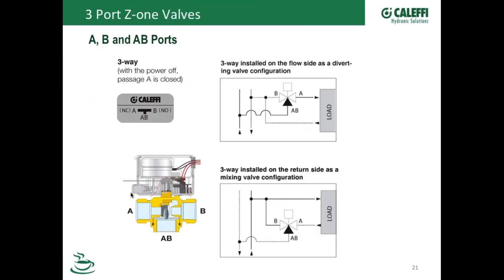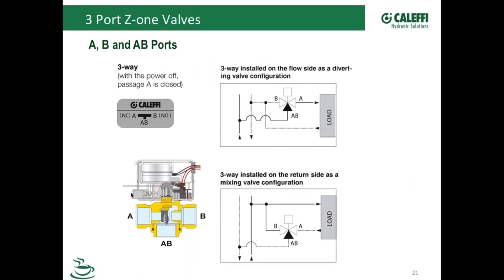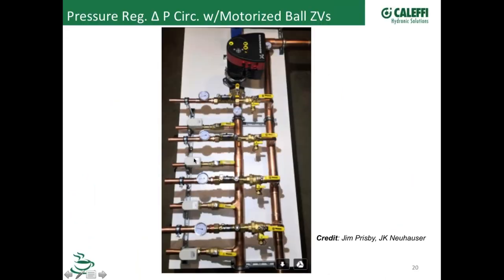But that 6442 series or 6443 series actuator is going to be a power open and power closed valve, which a lot of guys are used to the power open spring return, or power whatever direction spring return. So that's where you really gotta think about your controls when you use a valve like this, because you do need power to open it and power to close it. We also still include an end switch on it, like we have available on our Z-ones, but like I said, the wiring is just a little bit different. But even with standard components, you can make these zone valves work with a single pole double throw relay, where you're constantly powering one pole of the relay, or the actuator, and then as the relay switches, it'll power the other side of things.